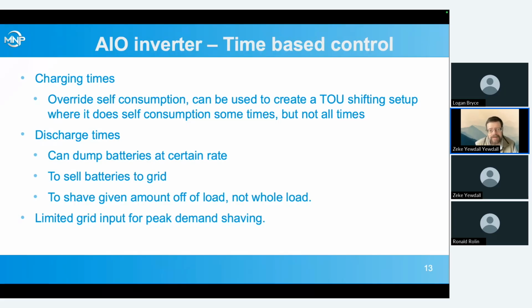But if you know that you might have 12 kilowatts of your load and set it for a 12 kilowatt discharge, obviously that might be a stacked inverter system because it's more than 10 kilowatts of a single inverter. What it's going to do is sell 12 kilowatts continuously for that whole time, regardless of whether the load is that large or not, which means it's going to be selling your batteries to the grid. Now, if that's your intent, this works pretty good.